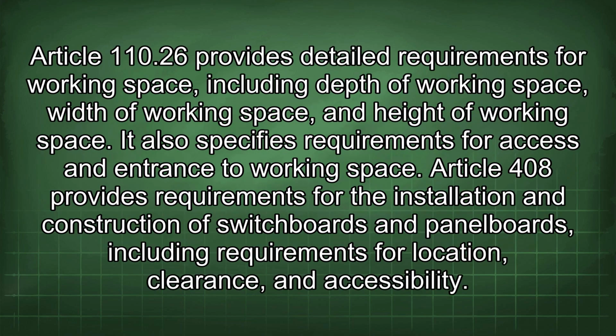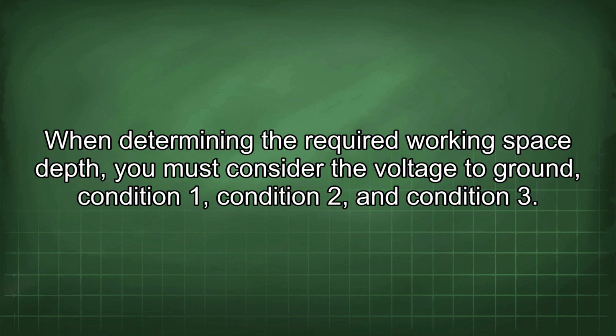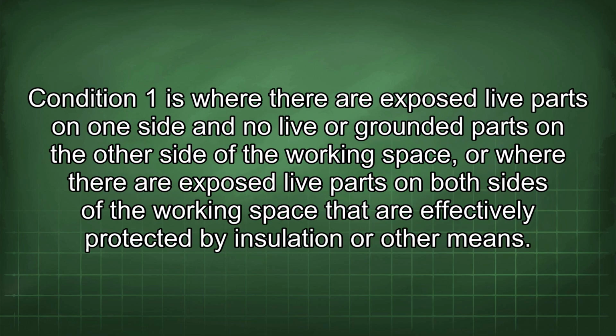Article 110.26 provides detailed requirements for working space, including depth of working space, width of working space, and height of working space. It also specifies requirements for access and entrance to working space. Article 408 provides requirements for the installation and construction of switchboards and panelboards, including requirements for location, clearance, and accessibility. When determining the required working space depth, you must consider the voltage to ground: Condition 1, Condition 2, and Condition 3. Condition 1 is where there are exposed live parts on one side and no live or grounded parts on the other side of the working space, or where there are exposed live parts on both sides of the working space that are effectively protected by insulation or other means.